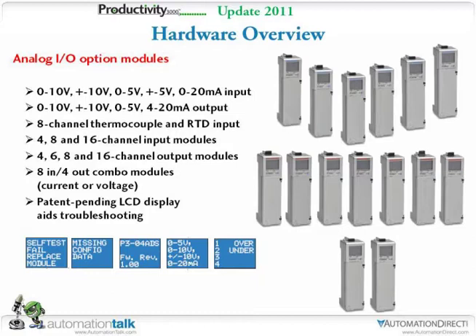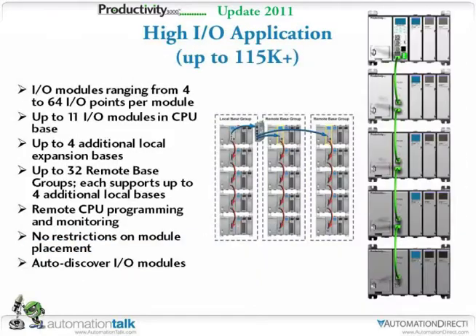Right. That is probably one of the most helpful things for a maintenance guy. Just to be able to walk up to the analog card, push a couple of buttons, and see what the card's actually reading on a given channel. Yes. He doesn't have to dig around the PLC program. He doesn't have to go find anything. He just walks right straight up to the card and pushes the button for the display, cycles through the display until he gets the I/O point in the display format that he wants, and he can see what's happening on that card right there without ever having to touch the PLC program. Right. All right, move along real quick.